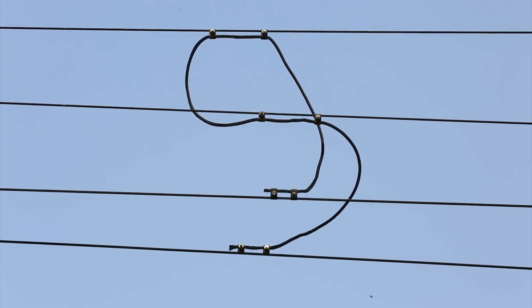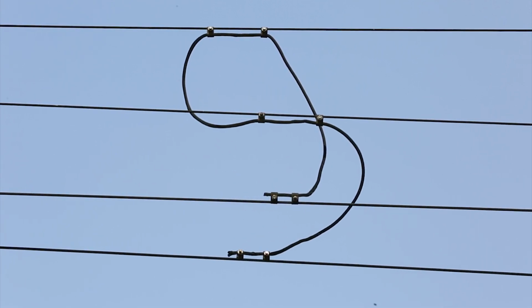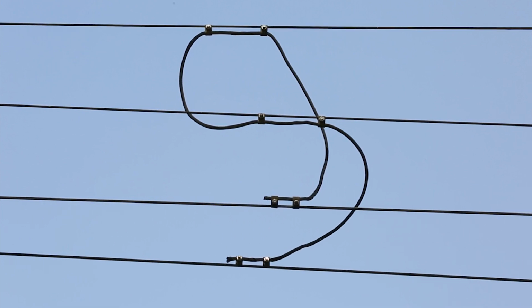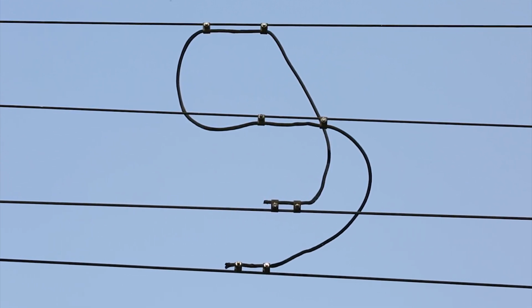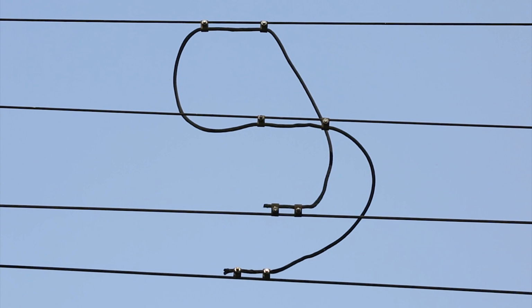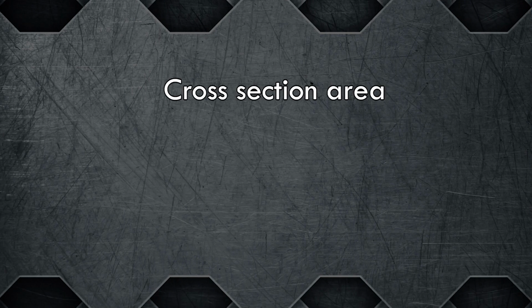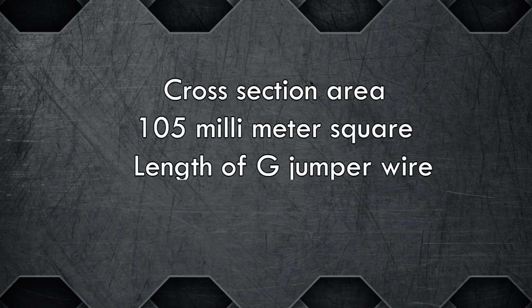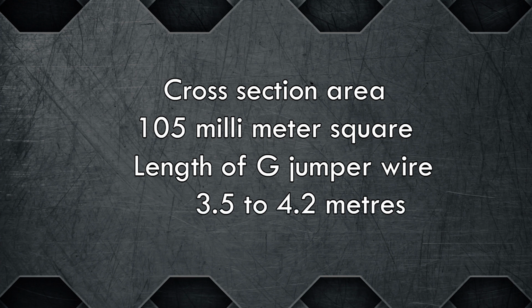G-jumper, also known as continuity jumper. G-jumpers are provided at uninsulated overlaps to provide continuous paths for electric supply. Cross-section area: 105 mm square. Length of G-jumper wire: 3.5 to 4.2 meters.